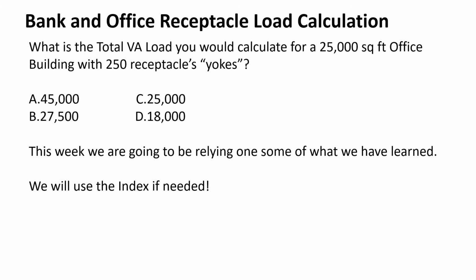Let's do a bank and office receptacle load calculation. What is the total VA load you would calculate for a 25,000 square foot office building with 250 receptacles? And we're talking about the yokes. Okay, so we've got some options here. Nothing stands out right away.